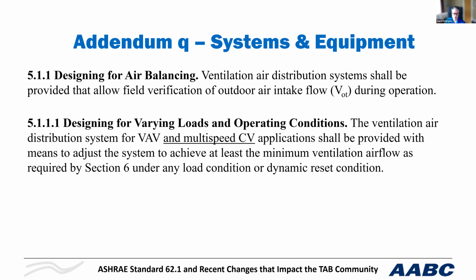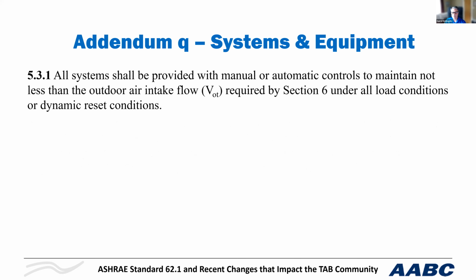This is to meet energy standards and energy codes. So basically what I'm saying is you can no longer have a fixed damper, a fixed opening, because you have dynamic systems and it's changing. So you have to have a modulating damper, you have to have logic, and this logic has to be closed loop control. Otherwise, you're not going to maintain the minimum flow rates that you need to. In addition to that, demand control ventilation requirements have significantly increased over the last 20 years.